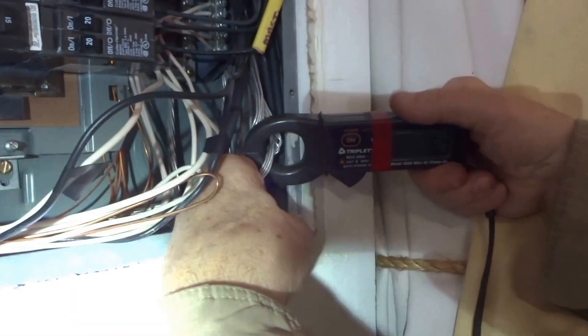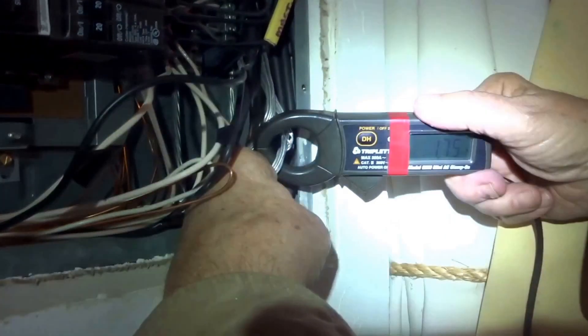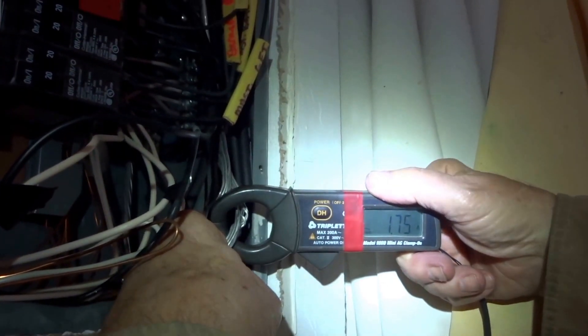Stephen, I see we're clamping the ground wire. We're clamping the ground wire to one of the condensers, and it is showing 1.7 amps of current on the ground.